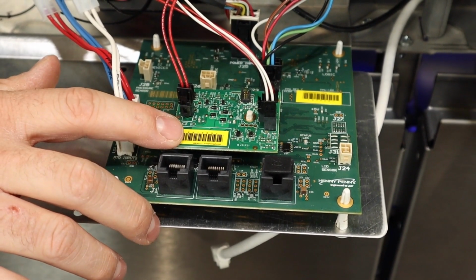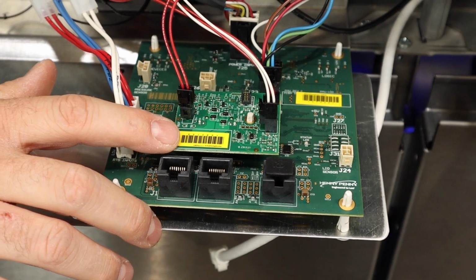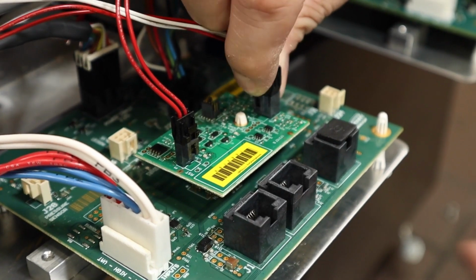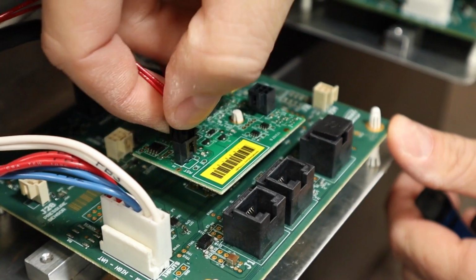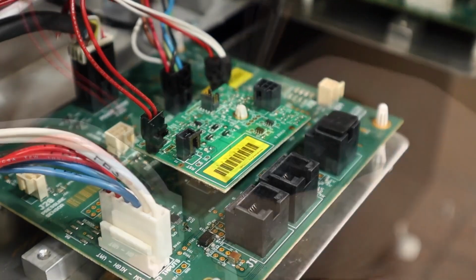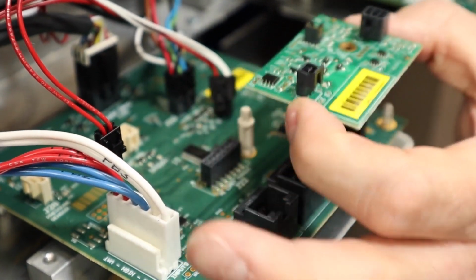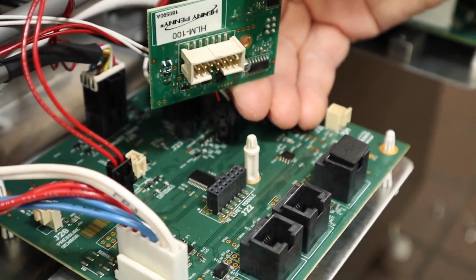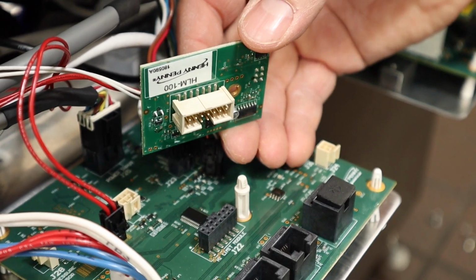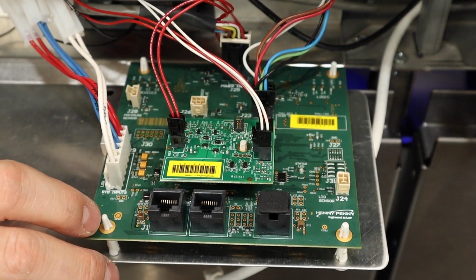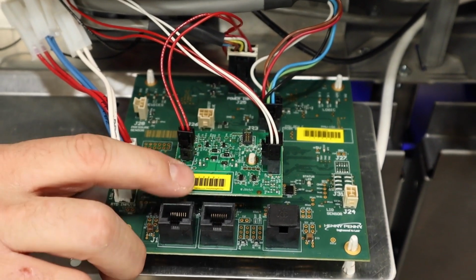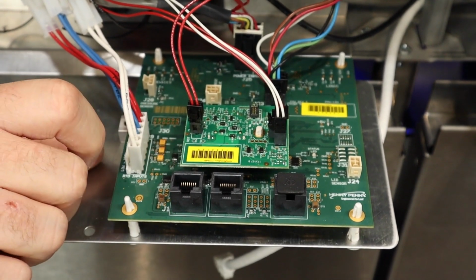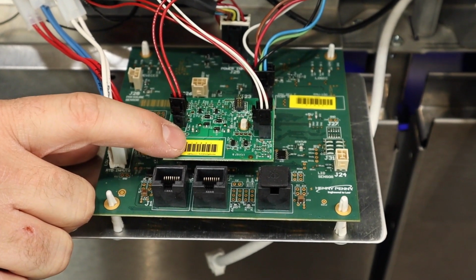However, if it doesn't, we want to go ahead and power the unit down for safety, and then we want to disconnect our connectors here, and then we're going to pull this PCB off of our PMU board and then reconnect it, so basically we can clean those connections there, hook everything back up, power it up, and see if that took care of the issue. If it didn't, it's going to wind up being a problem with our high limit PCB board here.